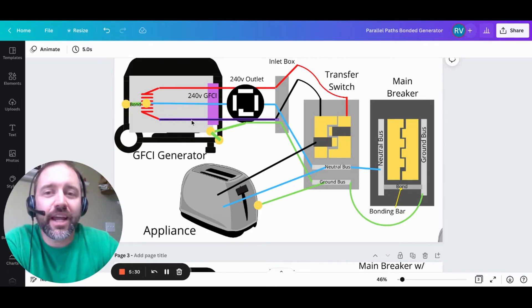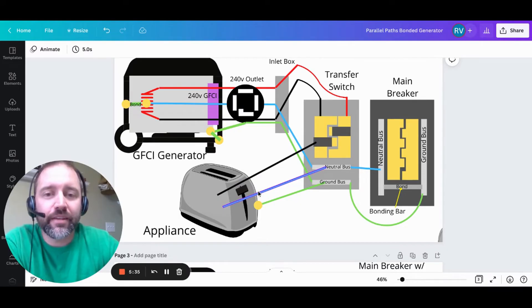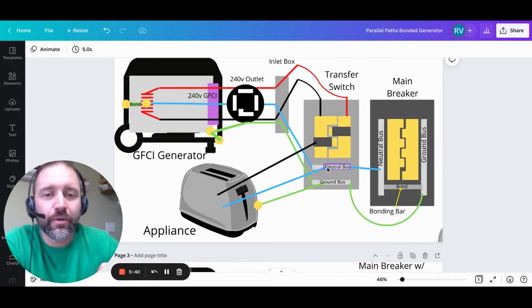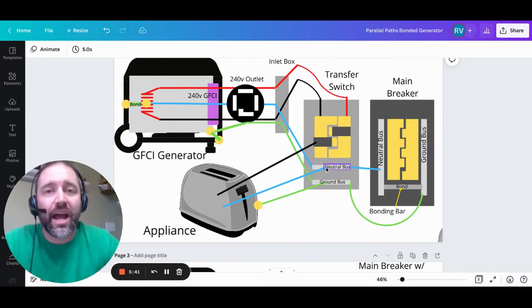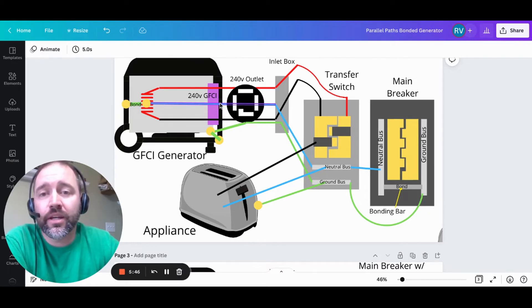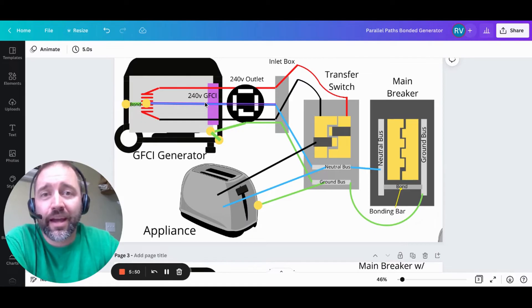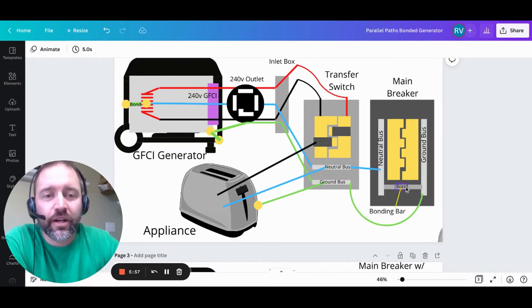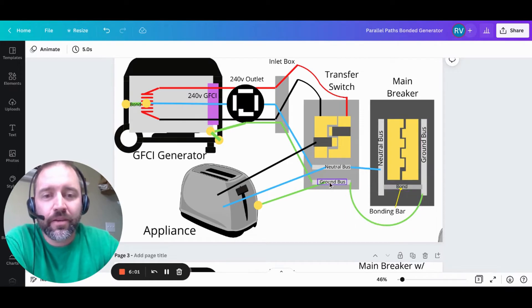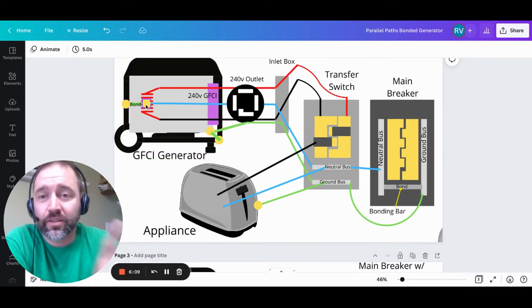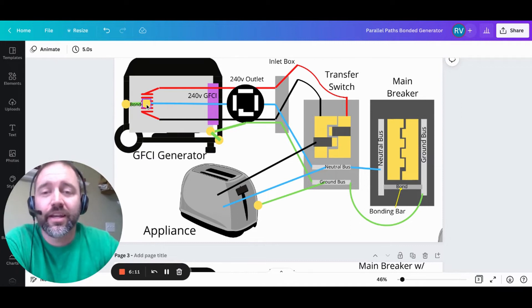So let's follow what's going on here. We have our 7 amps going out on the black, comes down just like before. It does work. 7 amps goes up this neutral. It hits this neutral bus. Here's where it diverts. We're going to have perhaps 5 amps that continue up the neutral through the outlet here, through the GFCI. So you have 7 out and only 5 coming back. At this point, it's going to trip. Where'd the other two go? The other two jumped over to this neutral bus, across the bond, to this ground bus, back on the ground here. Ground, as you're following it, down here to the generator itself, and it bounces back to the neutral point, the neutral bond, right here.